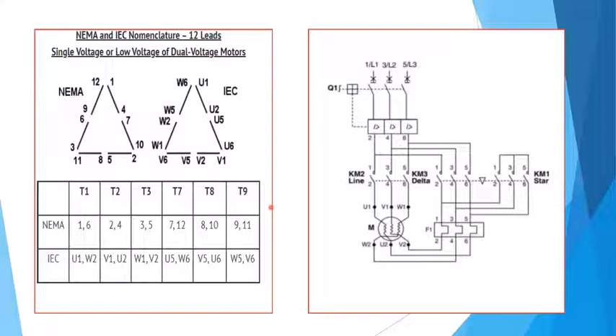This is the way a lot of it was done in Europe, and you'll see the IEC nomenclature. These are the numbered lead numbers, and a lot of them you'll have like a 12 lead motor. Well, they were doing this again to reduce the inrush power. So they call this Y delta start. You can either do it on a 400 volt system, 480, or 230 volt systems. But literally what was happening, it was taking this circuit, and this is like one set of the phases. If it was on the high voltage side, you'd tie 4 and 7 together. So this would give this motor, when it was actually operating, to be running at 480 volts here.